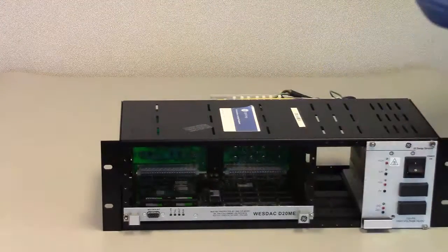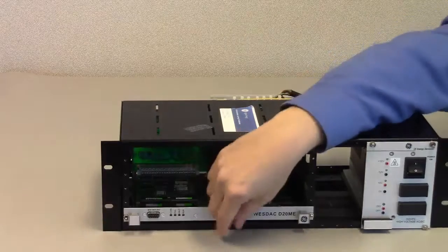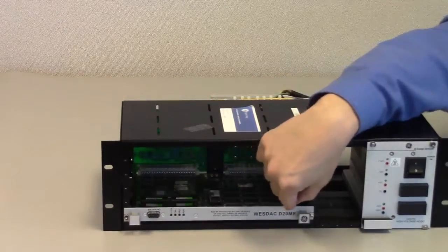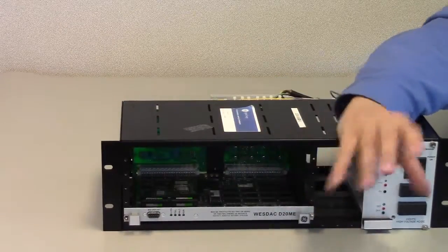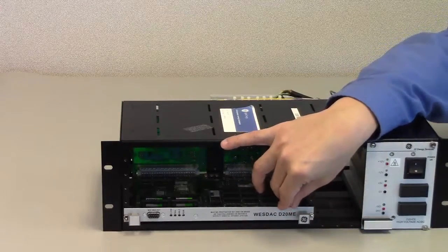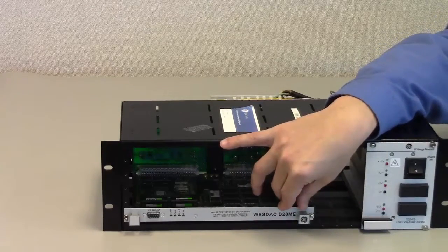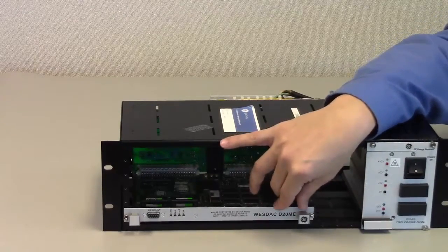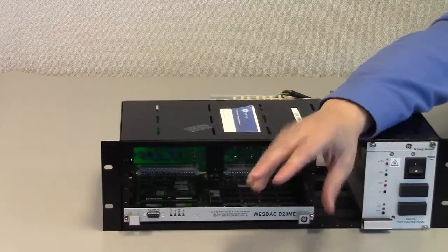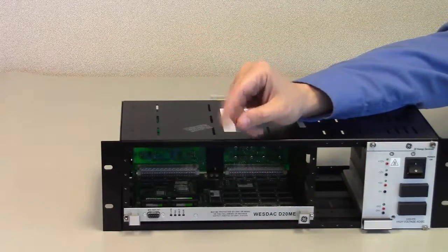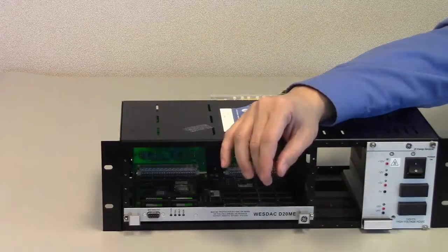There's only one card in this chassis, and this card is the WESDAC D20ME, versus what we've seen in the D200 which is the WESDAC D20ME2 card. The difference between the ME and the ME2 is that the ME2 allows for RS-485 and serial ports, while the ME is only RS-232 communication.